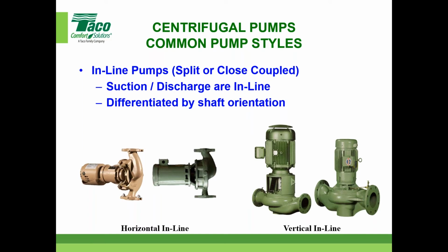Anything to add, Rich? Well, I think they're asking about speed. Is there a minimum pump speed? I think the answer is generally 20 hertz. We don't recommend running the pump lower than 20 hertz. It's not because the pump can't, it's because you need to protect the seals. The seals need water or flushing in order to operate correctly or to keep going.